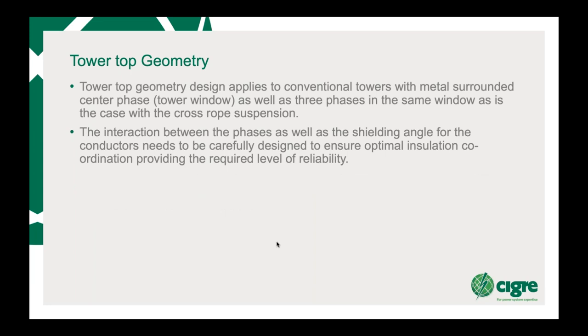Looking then at the tower top geometry, that applies to conventional towers with a metal surround center phase. In other words, if you've got a cross-shaped tower where all three phases are in the same window, you don't really have a tower top geometry issue. But if you've got normal conventional towers with the center phase going through the middle of the tower and the other two phases on the outside, you then need to take into account your insulation coordination between the center phase and the tower window. So the interaction between the phases as well as the shielding angle for the conductors needs to be carefully designed to ensure optimal insulation coordination. So you need to ensure that you have an angle of 30 degrees or less cover for your phase from your shielding angle, and preferably a negative angle rather than a positive angle is better.